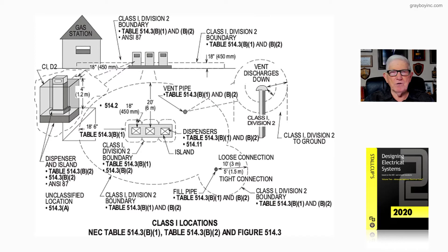But basically this just shows in the horizontal direction, 20 feet out, is a Class 1 Division 2 location up to 18 inches as you see there. Again, in our Table 514.3B1 and B2.